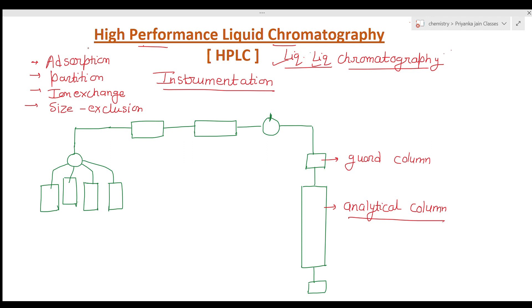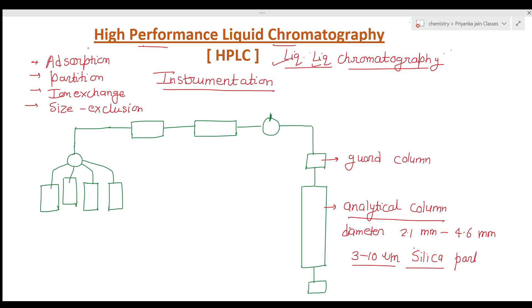The most important type of column used in HPLC is made of stainless steel and its diameter is between 2.1 mm to 4.6 mm. These columns are packed with porous silica particles of 3 to 10 micrometer diameter. These silica particles may be of spherical or irregular shape.